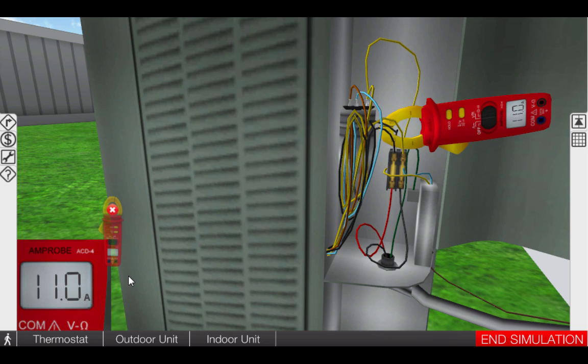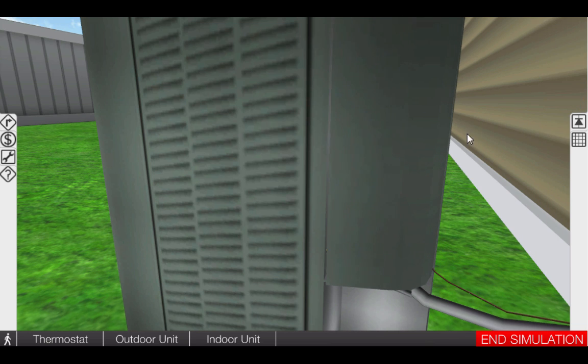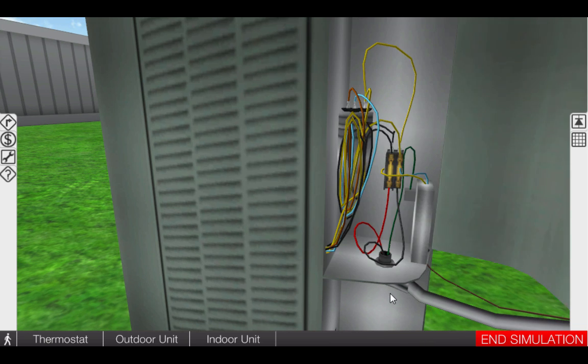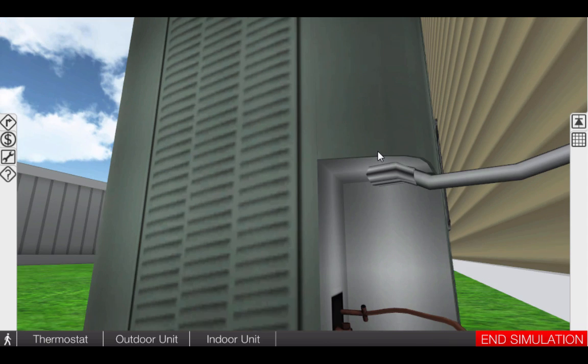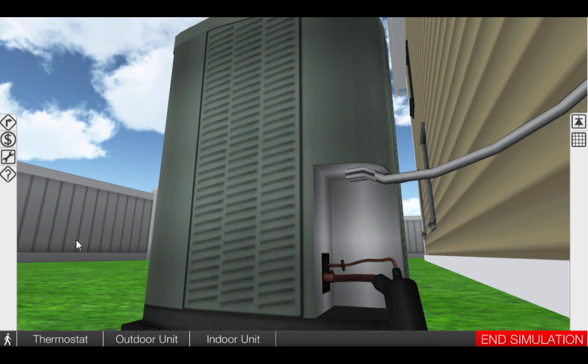We are going to put the clamp-on ammeter away now that we have verified that the compressor and condenser fan are operating. With all electrical loads operational, this means that we have a mechanical problem. Our next step is to check refrigerant pressures and superheat.